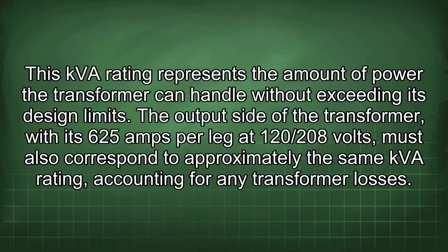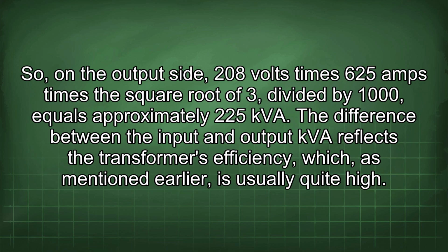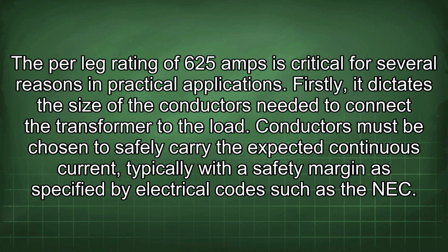The output side of the transformer, with its 625 amps per leg at 120/208 volts, must also correspond to approximately the same kVA rating, accounting for any transformer losses. So, on the output side, 208 volts times 625 amps times the square root of 3 divided by 1000 equals approximately 225 kVA. The difference between the input and output kVA reflects the transformer's efficiency, which, as mentioned earlier, is usually quite high. The per leg rating of 625 amps is critical for several reasons in practical applications.